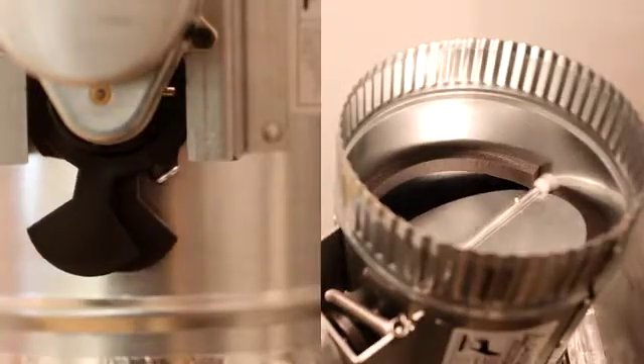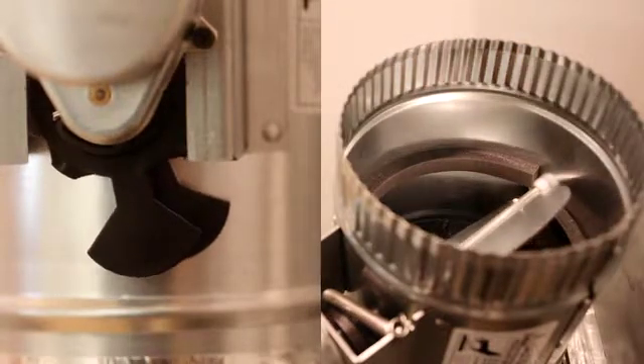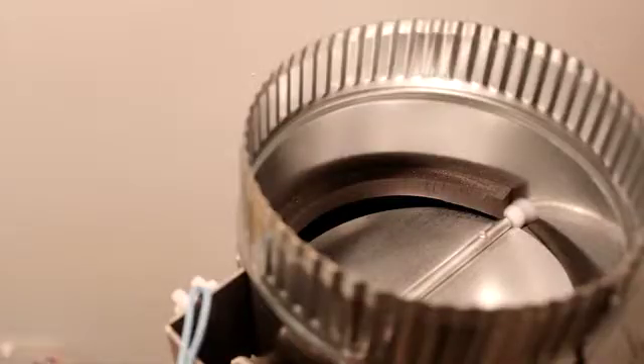Fresh air intake can be configured for 100% outside air delivery when the air handler is operational and closed off in between cycles. Or, it can be configured to deliver a minimum amount of outside air when unpowered and fully open once powered.